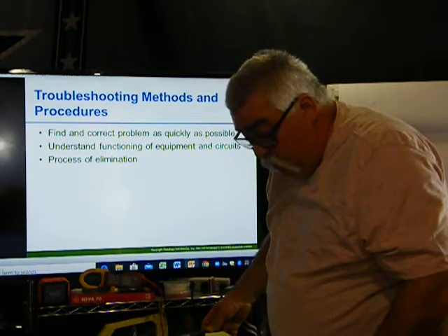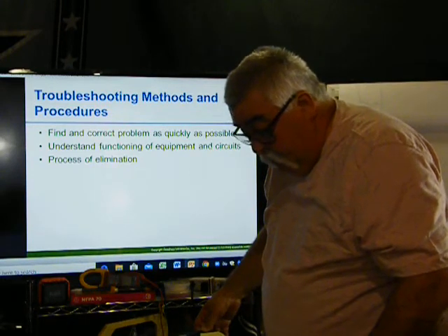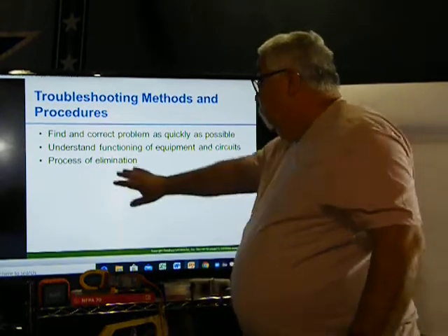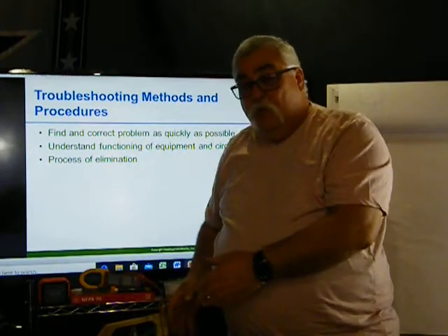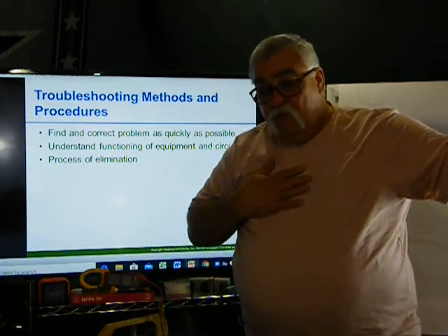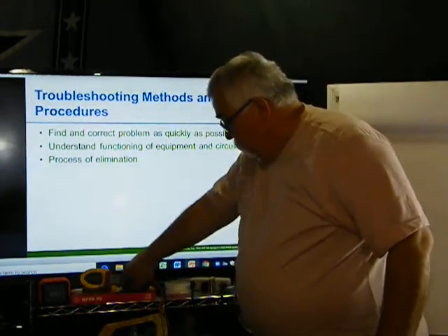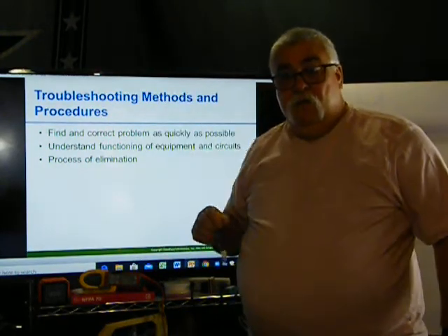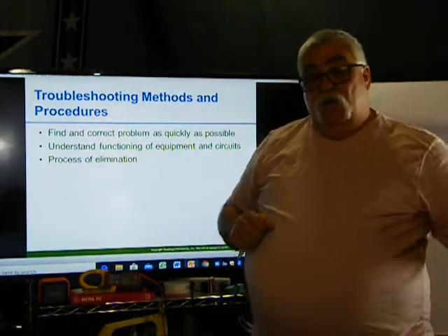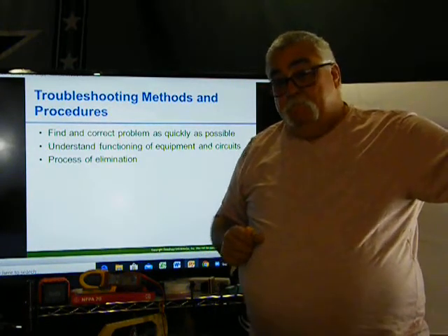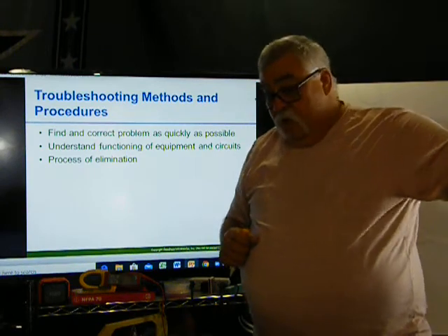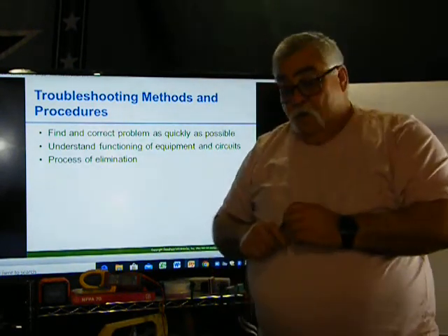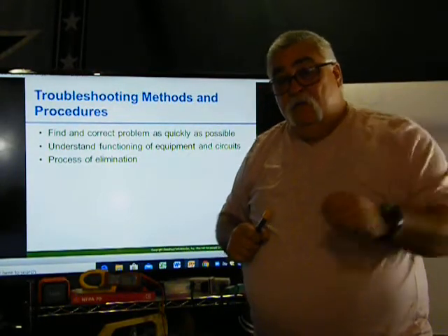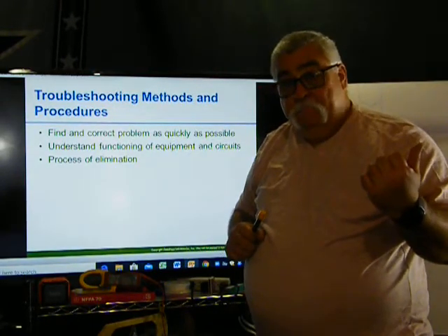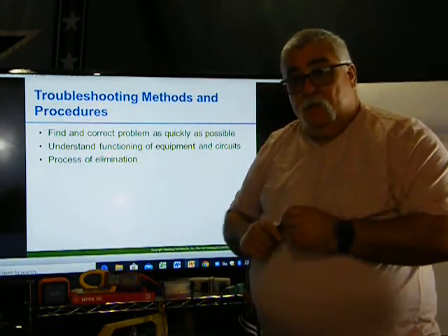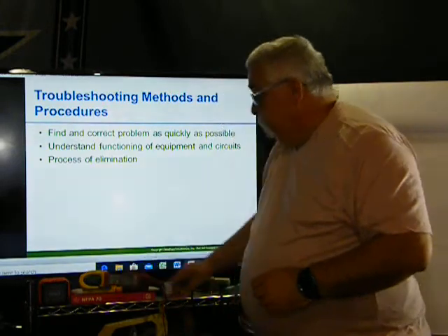Use the process of elimination. There will be certain parts that can be easily checked, for example, the power connection to the supply. Okay, where do you start? Machine stops working. My first thing: does it have power? Going over to the panel, does it have power in here? If my power's there, I still go back and check my power from the supply side. It's off the main breaker. If it's off the breaker, is it feeding that motor? Even though there's a disconnect, at the breaker where it starts off, is there power there? Is power getting to the disconnect? Process of elimination.